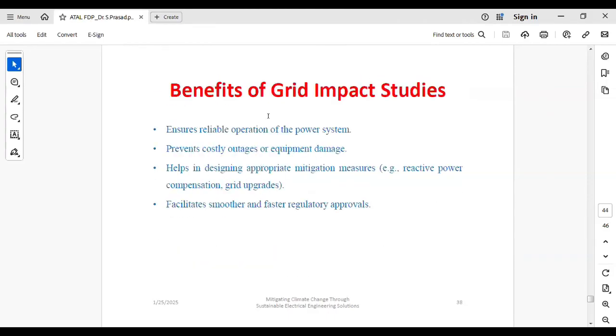So these are the benefits of the grid impact studies. The most important is that it ensures reliable operation of the power system and prevents costly outages or equipment damage. Obviously, if you want to conduct this test, and suppose some fault has happened, then it may damage the equipment also. Breaker rating, transformer rating, everything will be decided. Breaker rating will be decided based upon the short circuit current. So like that.